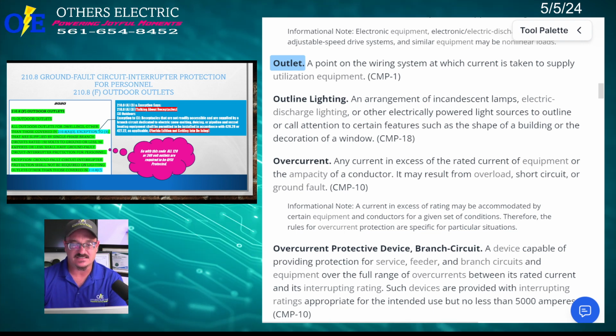So let's read this exception. 210.8(A)(3), talking about receptacles, outdoors. Okay? Exception to 3: receptacles that are not readily accessible and are supplied by branch circuits dedicated to electric snow melting, de-icing, pipe and vessel heating equipment shall be permitted to be installed in accordance. So what they're saying is, the only thing that's excluded from this is stuff for de-icing, right? Critical stuff that needs to be on and not on GFCI, okay? So the exception doesn't pertain to us here.